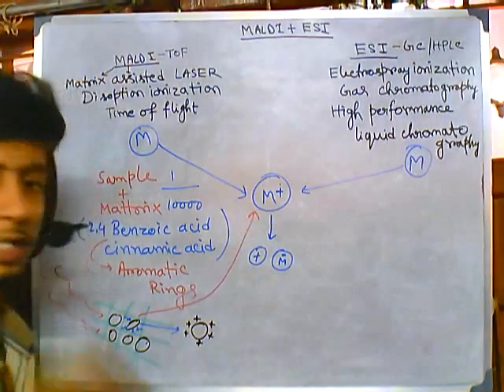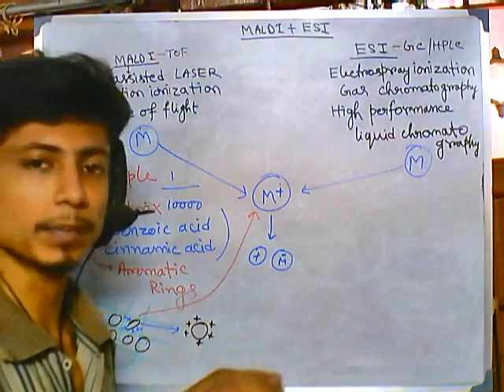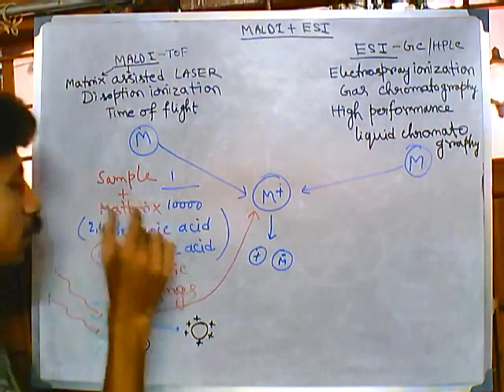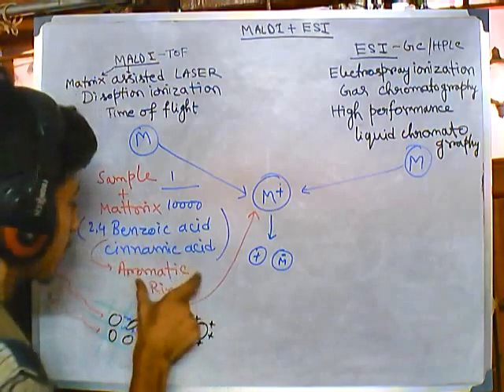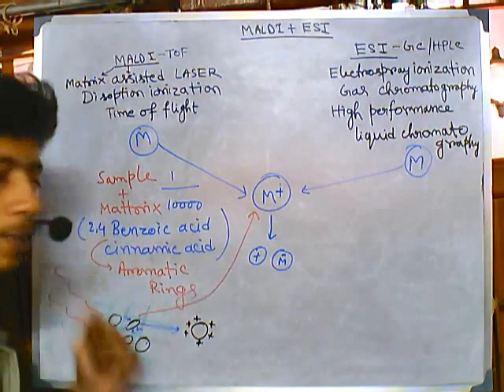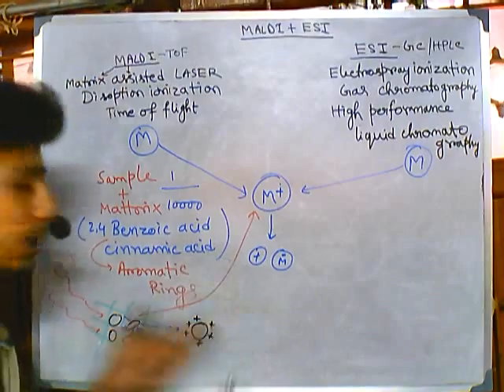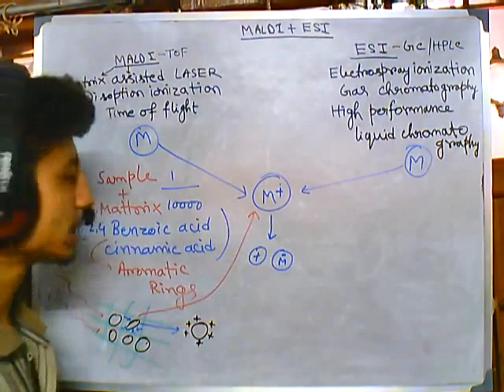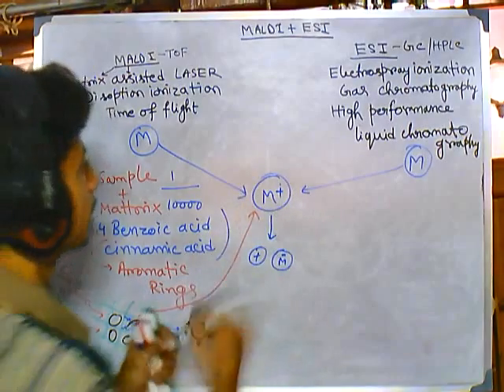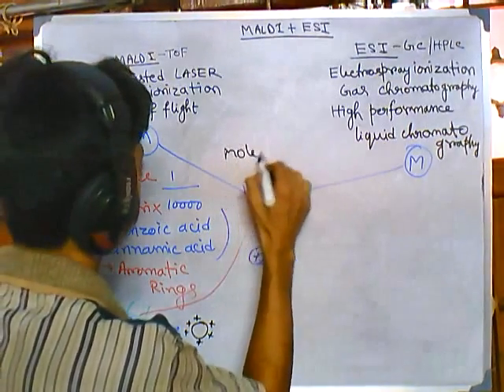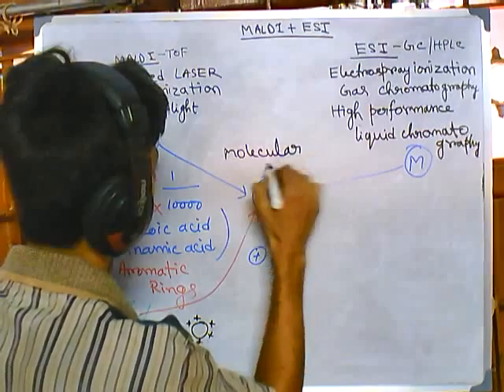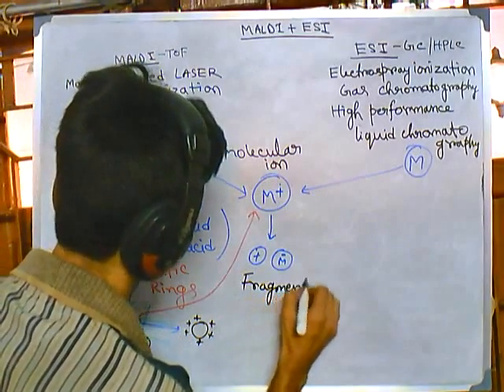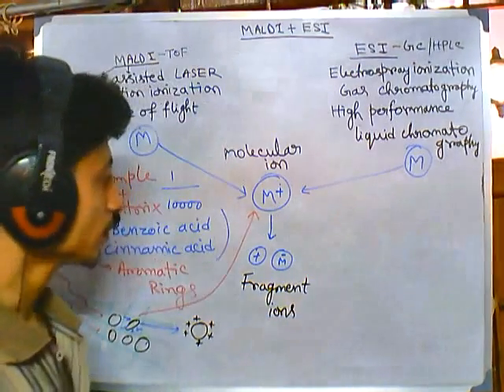So this is the procedure: we are not directly utilizing laser on the sample; instead we hit the laser onto the matrix. For that we prepare the matrix with chemical compounds having aromatic rings — benzoic acid and cinnamic acid — and they transfer the energy to the sample. The samples get ionized, desorb from the matrix, and generate the molecular ion M+. These further fragment into what we call fragment ions.